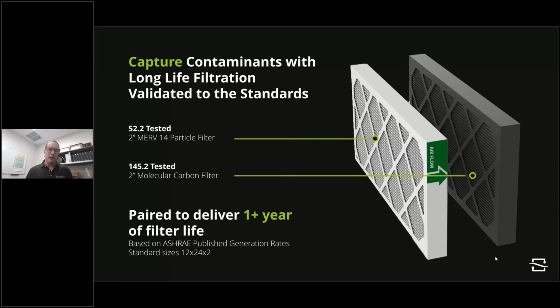And so as part of the standard, there are 2 tests that we had to run with our unit. The first test is quite simply, most people know it, but it's for the particles in the air, and that's related to 52.2. And so in our basic kit, we offer a MERV 14 2-inch thick, deep pleated panel rated at 50 for the 52.2 rating. And then additionally, we offer a molecular filter that's been substrated for aldehydes, and it's also got carbon in it to handle all those other VOCs in the air.